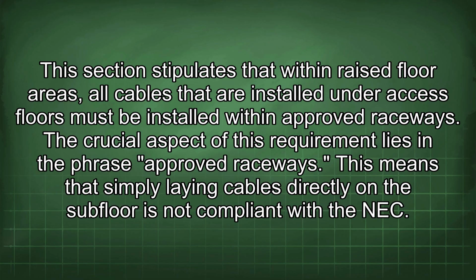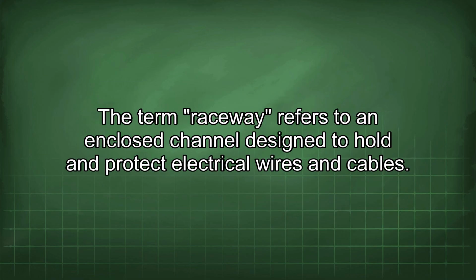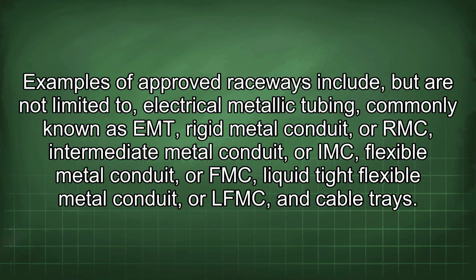This section stipulates that within raised floor areas, all cables installed under access floors must be installed within approved raceways. The crucial aspect of this requirement lies in the phrase approved raceways. This means that simply laying cables directly on the subfloor is not compliant with the NEC. The term raceway refers to an enclosed channel designed to hold and protect electrical wires and cables.